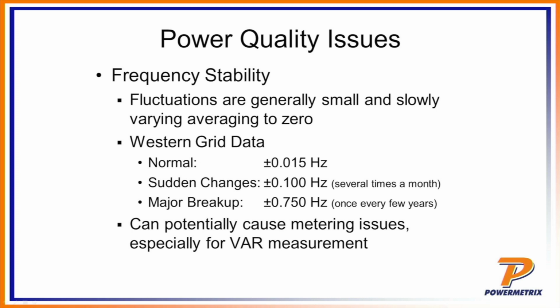This particular issue actually can cause metering issues, especially for VAR measurement, simply by the fact that a lot of meters were designed based around a 60 hertz clock coming into the system. There's been a lot of improvement in that over the last few years. We'll talk about harmonics here in a little bit. That pertains a little bit to this. But historically speaking, this could cause a lot of problems because the meters were designed really to expect a pure 60 hertz signal, and so any deviation off that frequency could cause the electronics to misbehave and cause metering issues.